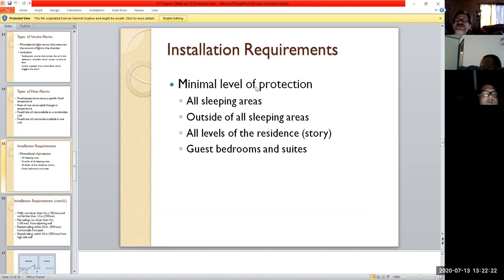So here's our minimum. You can always install extra smoke alarms, nothing wrong with that. But as far as the NFPA is concerned, these are the areas that absolutely have to be covered—there has to be coverage within the radius of the alarm for these different areas. Pretty much all sleeping areas, guest bedrooms, basically anywhere anybody's going to be sleeping needs an alarm protecting it, as well as all levels of the residence—basement, first floor, second floor, that kind of thing. Each level has to have some protection even if there are no sleeping areas on that level. So if all sleeping areas are on the second floor, you'd still need the first floor protected, though you'll probably have more alarms upstairs where the sleeping areas are.